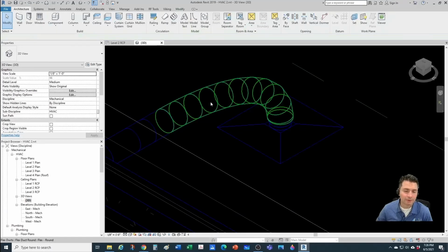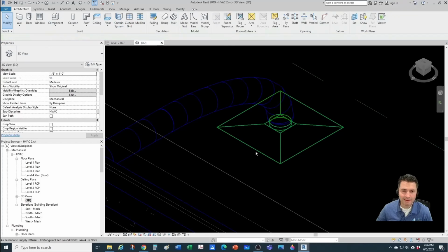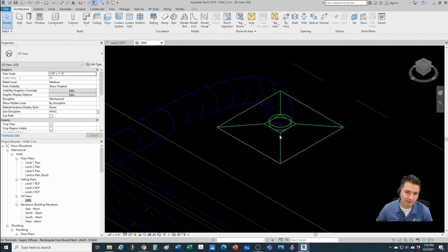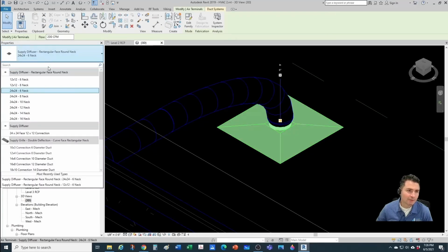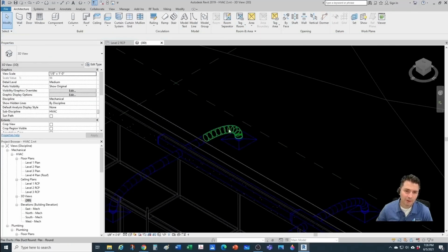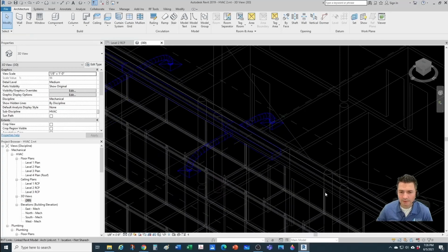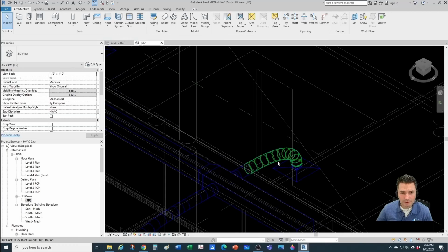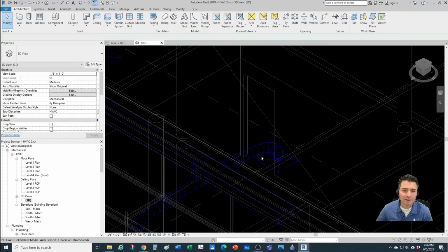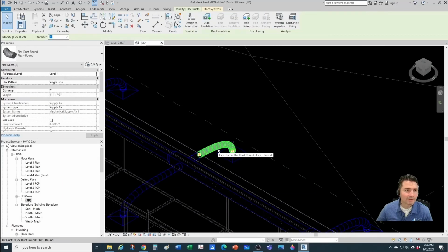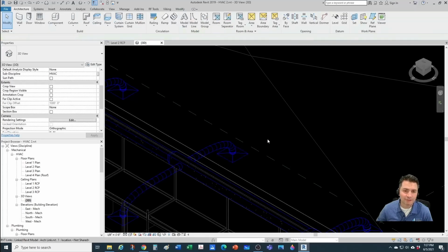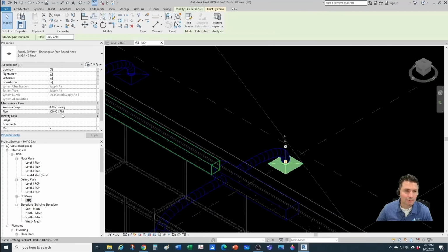Okay. Now, if you want to refine a little bit more, you can check your ductwork sizes against your diffuser neck. For example, in this case, you got 7 inches, and you have on this side 24 by 24 by 6. You're kind of constricting this at the end. So you may want to change this to 24 by 24 by 8 inches, and then probably resize your ductwork to have a smooth transition there. And for this piece here, you can tell that this duct actually was taken up to 8 inches. Notice that this one was taken up to 7 inches because this diffuser had 200 CFM. This one here had 300 CFM.